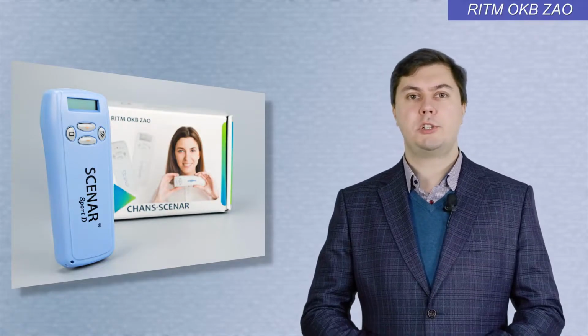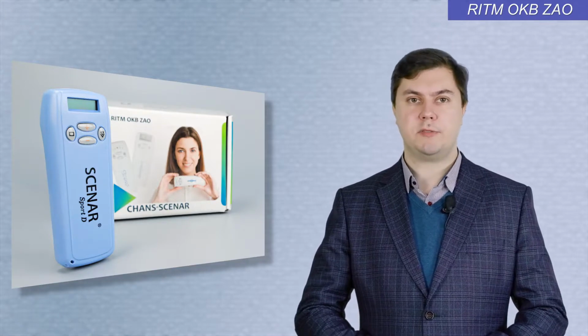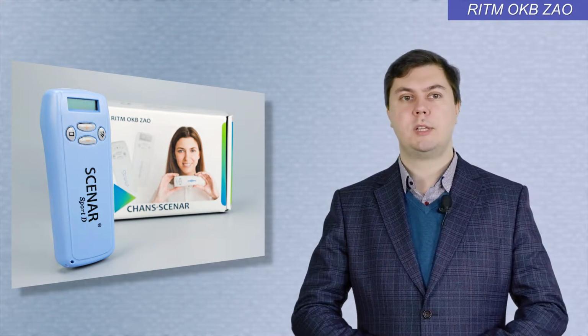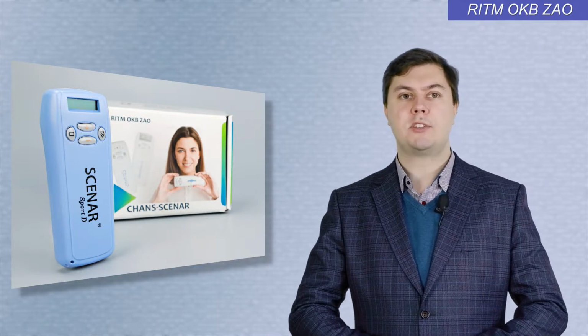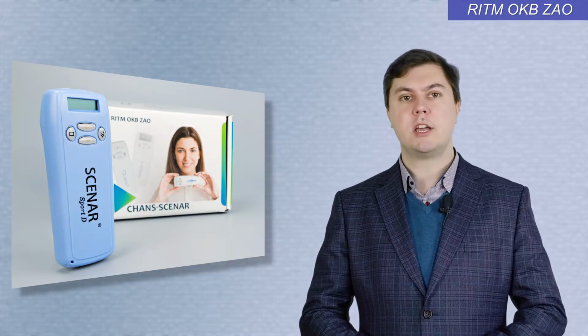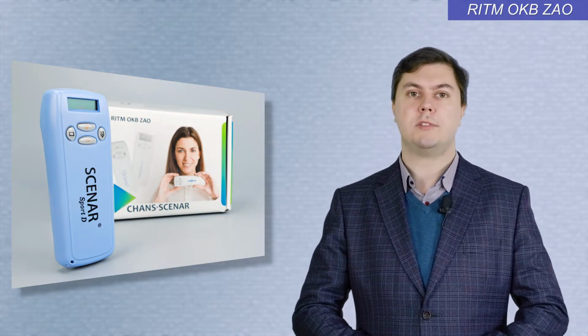Attention! When you switch on a preset, the treatment energy value is stored in the memory of your device. If you use the P2, the treatment energy may change automatically during the preset. When the preset P2 is switched off, the treatment energy goes back to the value that was set previously. In order to avoid uncomfortable sensations or pain, please decrease the treatment energy to minimum after you switch off a preset.